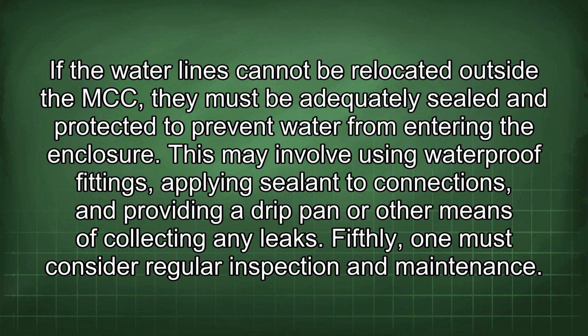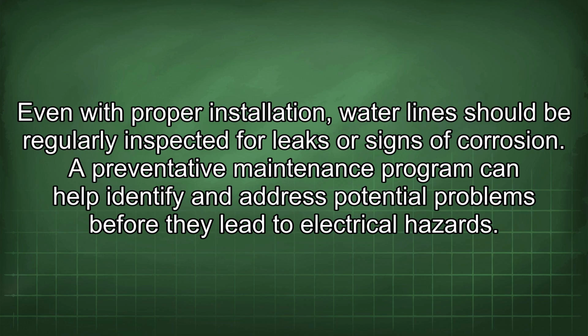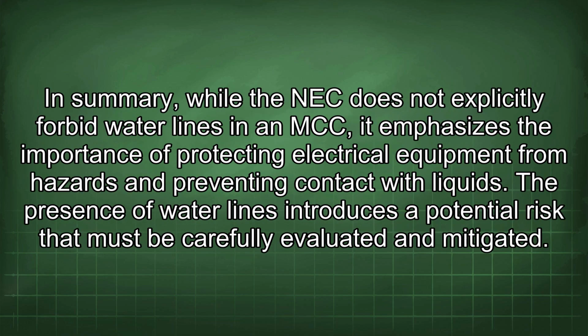Fifthly, one must consider regular inspection and maintenance. Even with proper installation, water lines should be regularly inspected for leaks or signs of corrosion. A preventative maintenance program can help identify and address potential problems before they lead to electrical hazards. In summary, while the NEC does not explicitly forbid water lines in an MCC, it emphasizes the importance of protecting electrical equipment from hazards and preventing contact with liquids. The presence of water lines introduces a potential risk that must be carefully evaluated and mitigated.